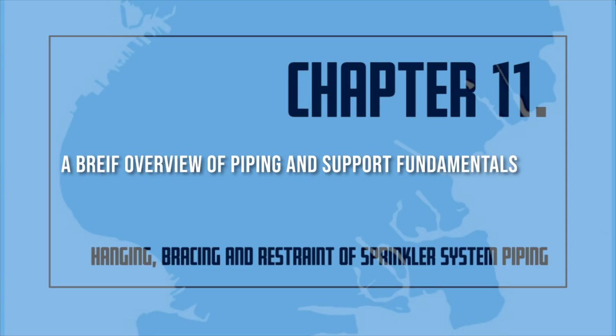The cumulative length of an unsupported arm over to a sprinkler head, sprinkler drop, or sprinkler sprig up shall not exceed 24 inches for steel pipe and 12 inches for copper pipe. System risers, vertical piping passing from floor to floor, shall be supported with riser clamps and hangers located within 24 inches of the center line of the riser. The distance between supports for risers shall not exceed 25 feet.